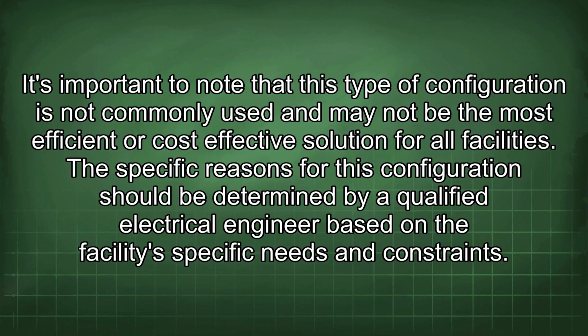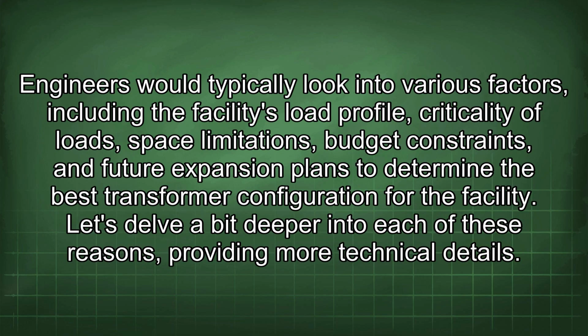It's important to note that this type of configuration is not commonly used and may not be the most efficient or cost-effective solution for all facilities. The specific reasons for this configuration should be determined by a qualified electrical engineer based on the facility's specific needs and constraints. Engineers would typically look into various factors, including the facility's load profile, criticality of loads, space limitations, budget constraints, and future expansion plans to determine the best transformer configuration for the facility.